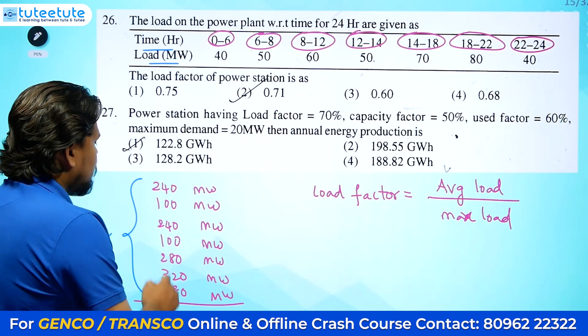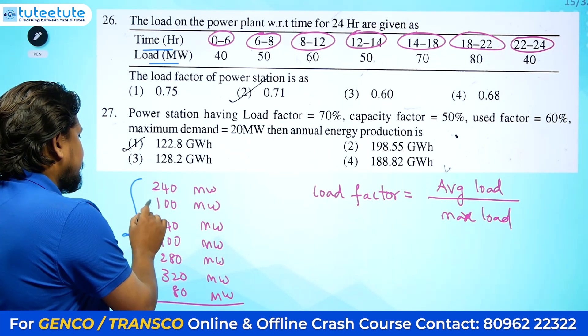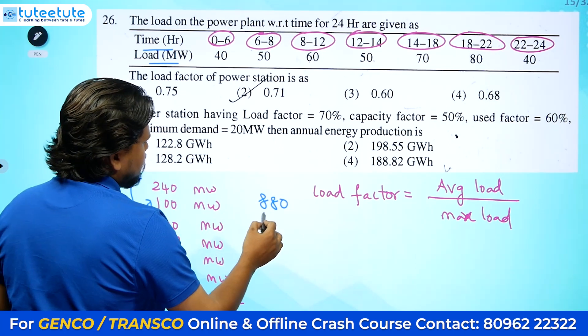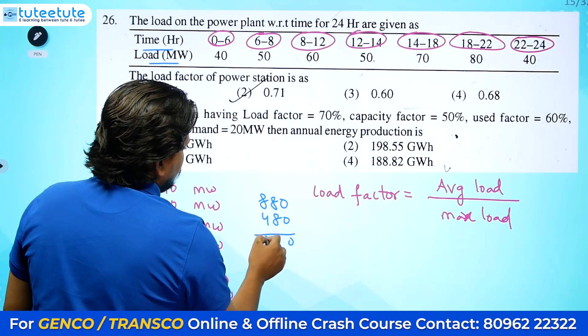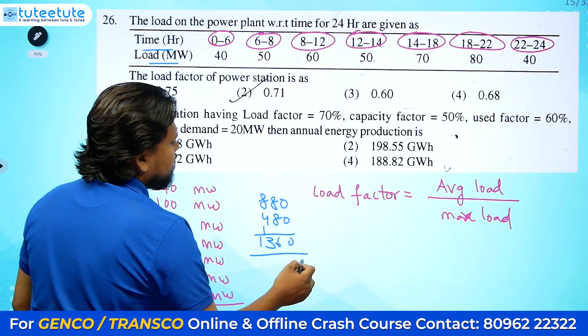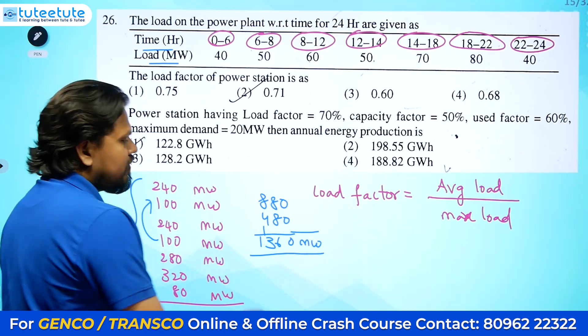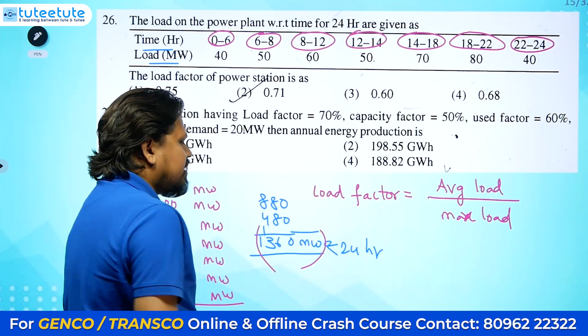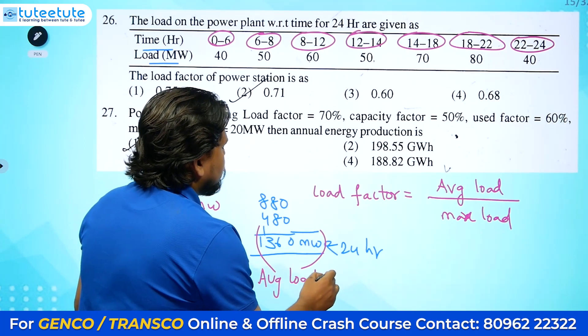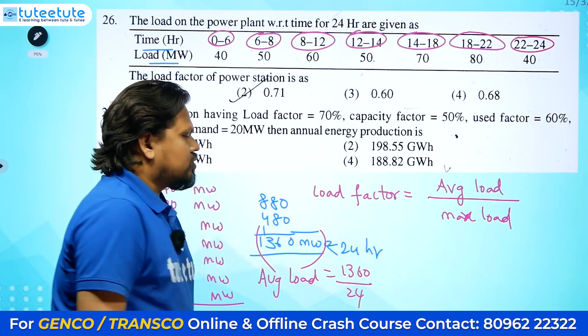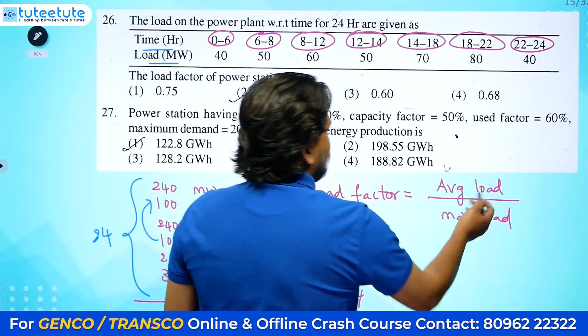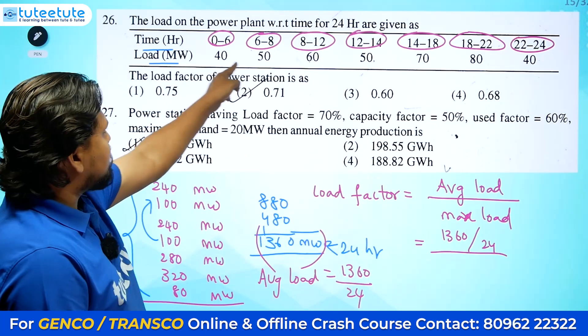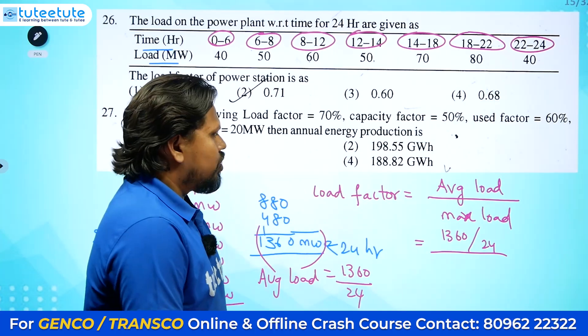Adding all these values: 240 + 240 + 100 + 100 + 280 + 320 + 80 = 1360 MWh total for the entire day. Average load equals 1360 divided by 24. You substitute this average load into the load factor formula: 1360 ÷ 24 divided by the maximum load. The maximum load is 80 MW.